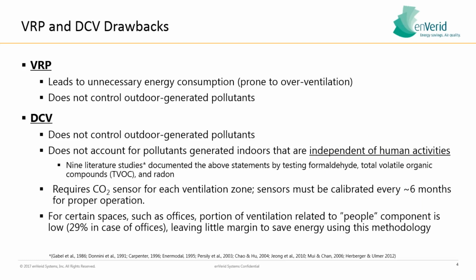Ventilation rate procedure often leads to unnecessary energy consumption. You're prone to overventilate with VRP, and it also doesn't control for outdoor generated pollutants. So for those of you who are in California right now with the wildfires and things like that, if you've got LEED buildings out there that subscribe to the ventilation rate procedure plus 30%, they're sucking in potentially huge amounts of outside air that have smoke and ash and all kinds of particulates, PM 2.5, in them. If you're designing buildings next to roadways, you're sucking in carbon monoxide and other roadway emissions and particulates.